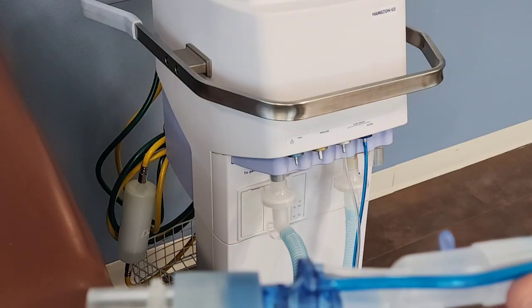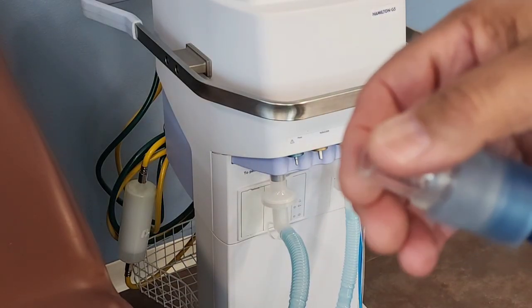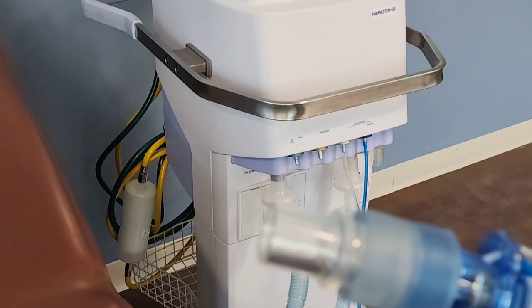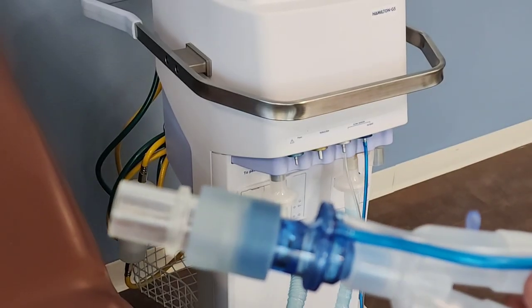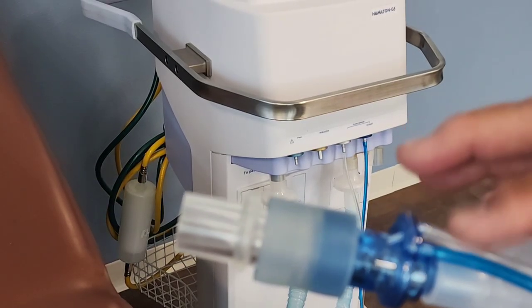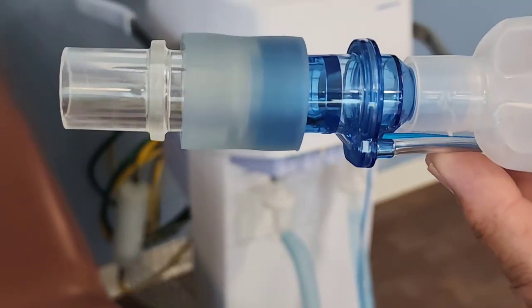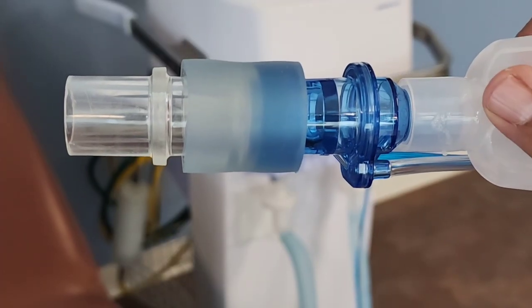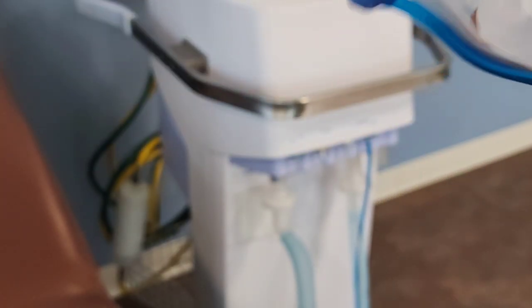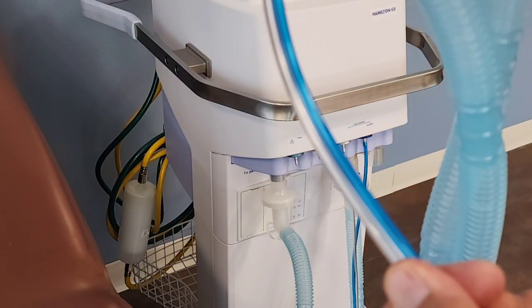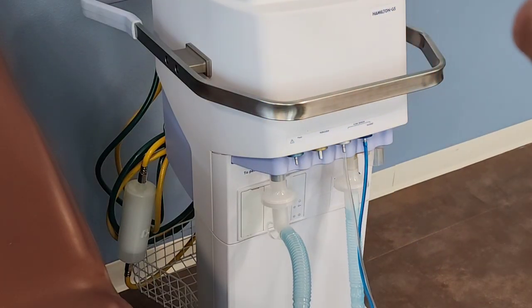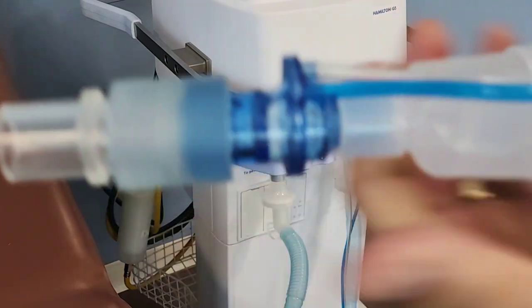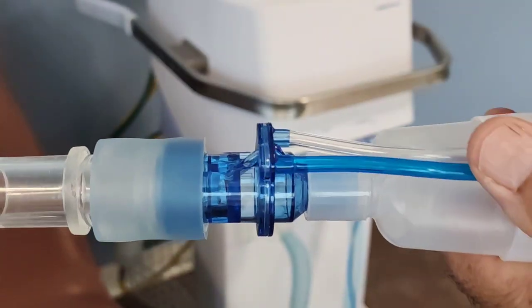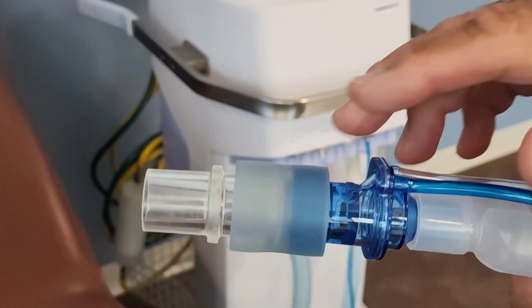We'll talk about this later on, but because there is humidification going on, we usually have an HME, heat moisture exchanger, connected here. And sometimes these units are connected to an external heater, which we don't have on here. But with the flow sensor tubing, if they are facing down like that, you can imagine what's going to happen if there's some moisture buildup in the circuit. That water can get into this flow sensor tubing and plug it up. So always have the tubing facing up when it's connected to the patient's endotracheal tube or tracheostomy tube.